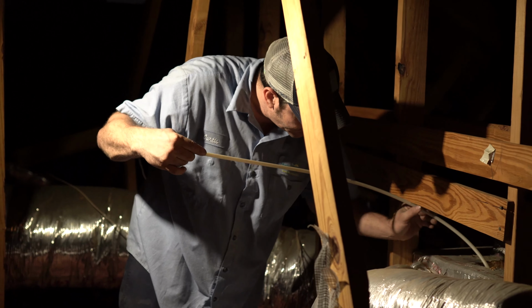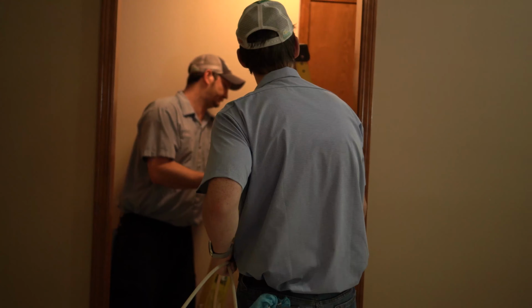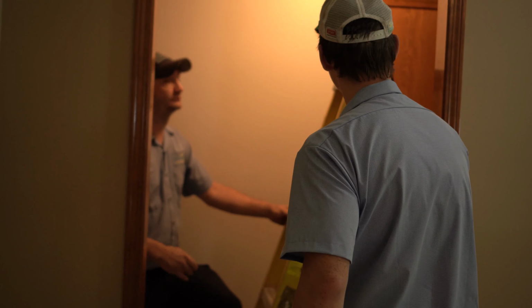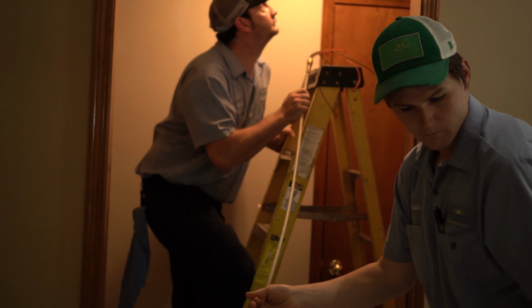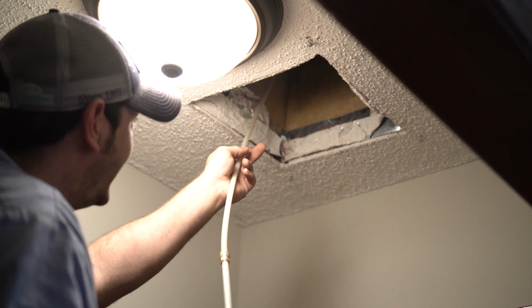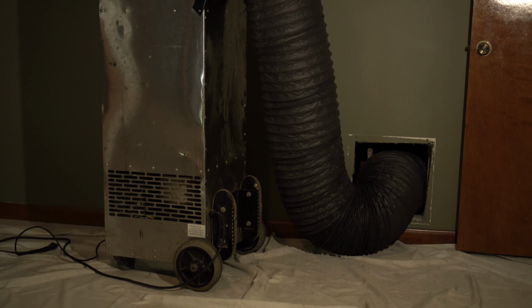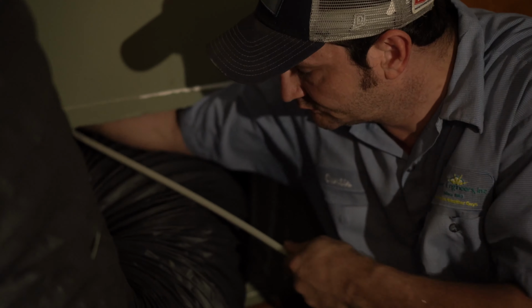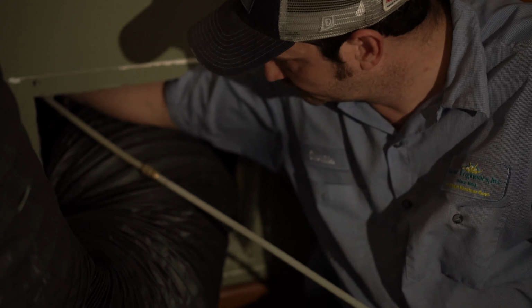Notice the technician here feeding the power rod assembly with whip on the end into the duct system to agitate the dirt and debris for cleaning. Here you can see the technician using a triple whip to clean the return branch line, feeding from the interior into the mixing box. He has the HEPA vacuum set up on a wall return, and we have the return system isolated from the air handler with cardboard blocking the coil section.